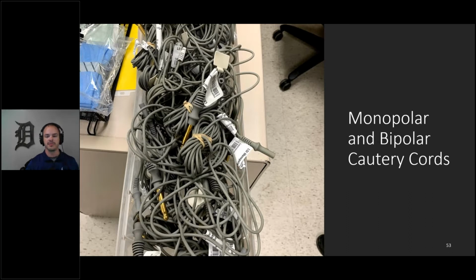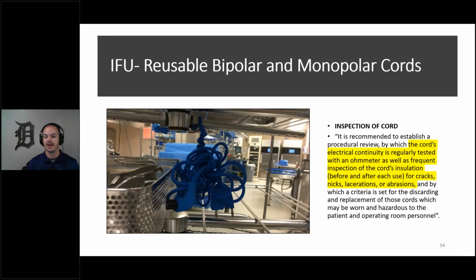And what about those monopolar and bipolar cords mentioned earlier? I'll tell you, those pictures of severed, burnt ones are real—I actually lived that in the operating room. I've seen them spark and break right in the middle of a procedure; it's pretty scary. Thankfully, in my experience, no harm occurred and no fire started, but you can definitely see how that could go wrong.